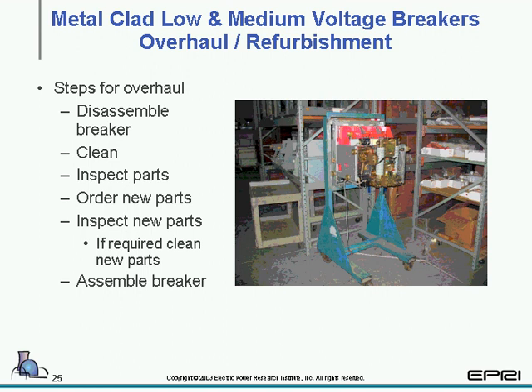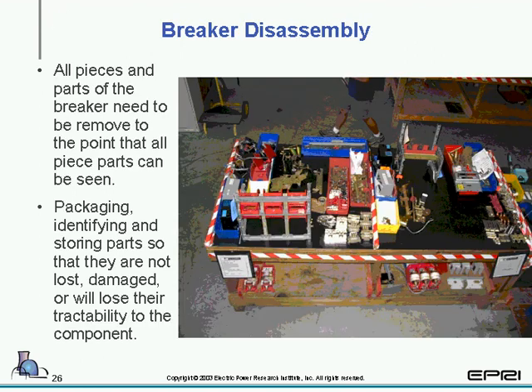We'll take a look at steps for overhaul. We'll take a look at disassembling the breaker, cleaning, inspecting the parts, ordering new parts, inspection of new parts, if required, cleaning new parts, and assembling the breaker. The very first one to take a look at is the disassembly. Most of the time, after you complete your incoming testing, at the end of that, you will completely disassemble the breaker. And as stated, all piece parts of the breaker should be taken apart and removed to the point that you can inspect or visually see all the pieces.